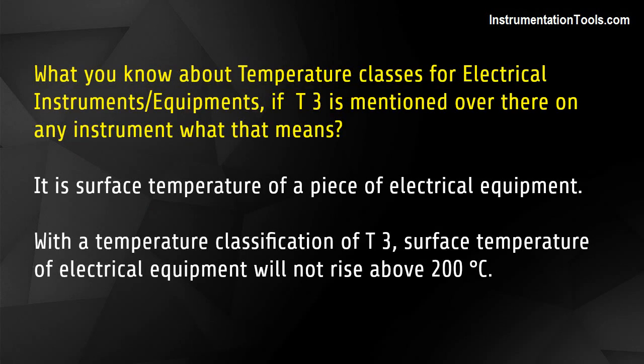What do you know about temperature classes for electrical instruments and equipment? If T3 is mentioned on an instrument, what does that mean? It is the surface temperature of a piece of electrical equipment. With a temperature classification of T3, the surface temperature of the electrical equipment will not rise above 200 degrees centigrade.